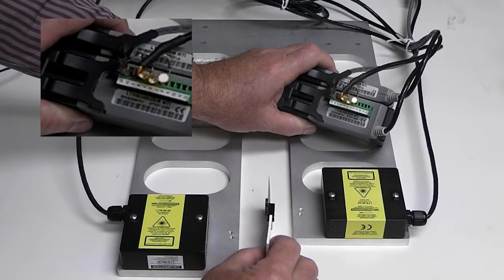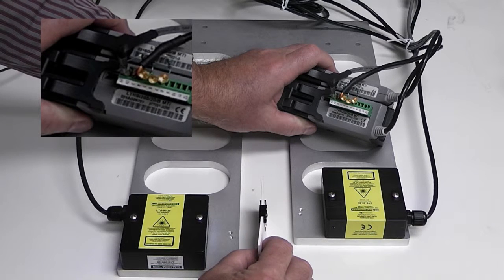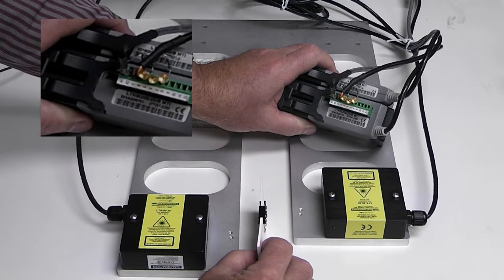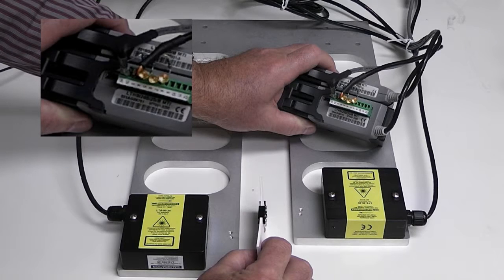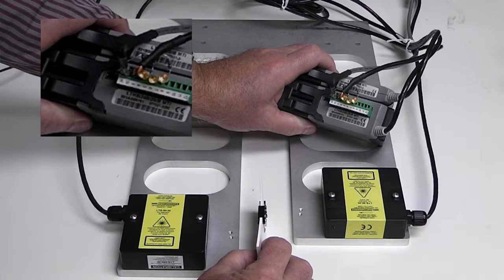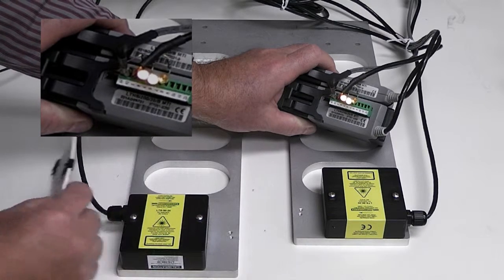I'm going to place the 80 thousandths thickness target in here, and we see there's no LEDs lit at all, which is indicative of no alarms or within range.